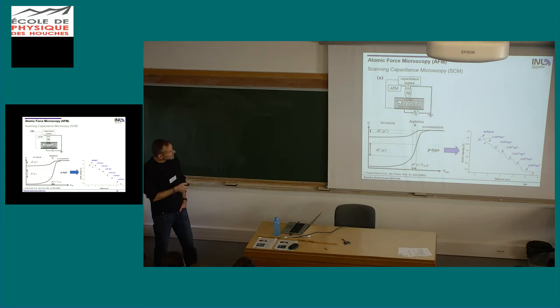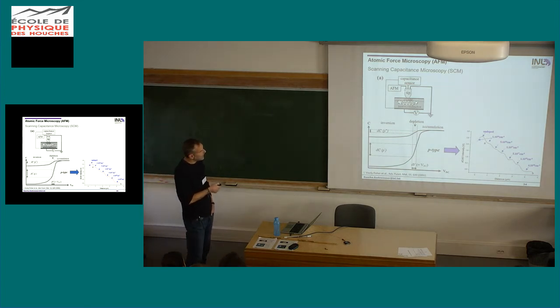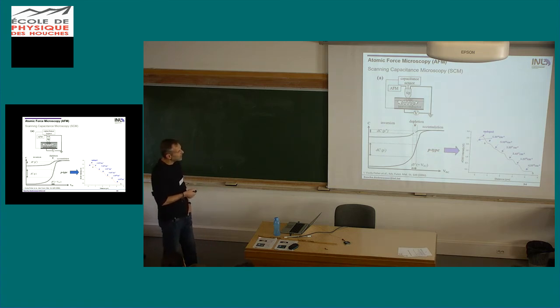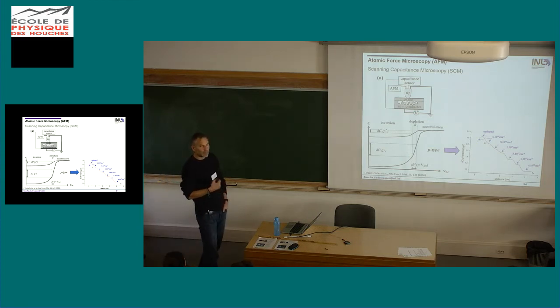So in the microscopy mode, what we do is we use an AC voltage that we apply at some DC bias here. So we oscillate between these two lines, and then we can immediately see that the oscillation in the capacitance for the highly doped semiconductor is very small, whereas for the lowly doped semiconductor we get much larger variation in the capacitance. So that means that if we have a large signal, we have a low doping, and if we have a low signal, we have a high doping.